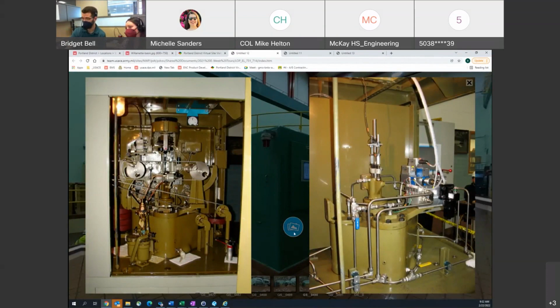Over time, as we've upgraded them, we've been able to remove some of those mechanical functions and turn them into digital controllers. These are hydraulic, high-pressure lines running to a digitally controlled proportional valve that pushes oil back and forth, with a feedback mechanism that tells us exactly where the hydraulic valves are located in that chamber - that's how we know what the governor is doing and how we control it to go more open or more closed.